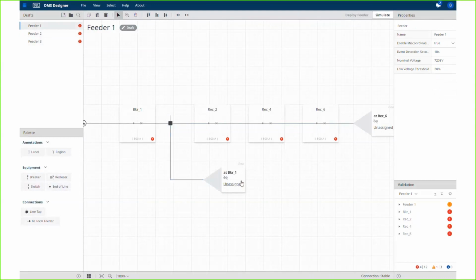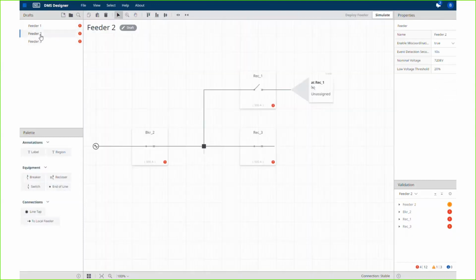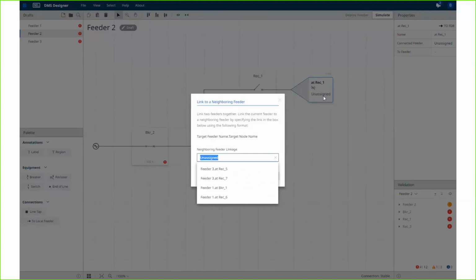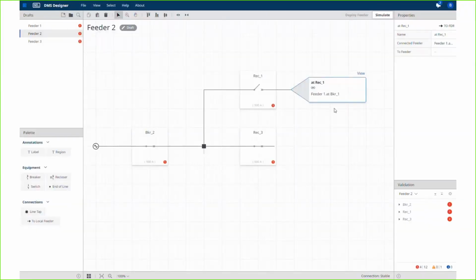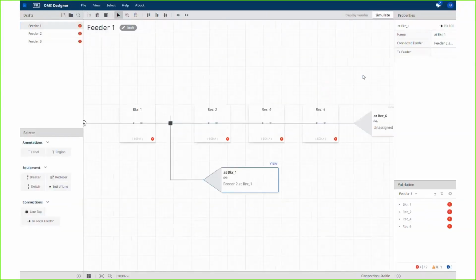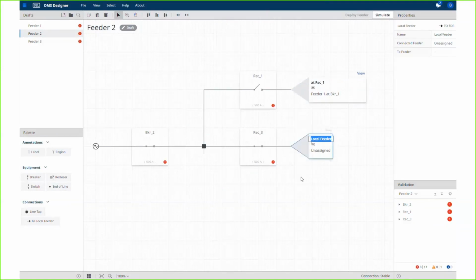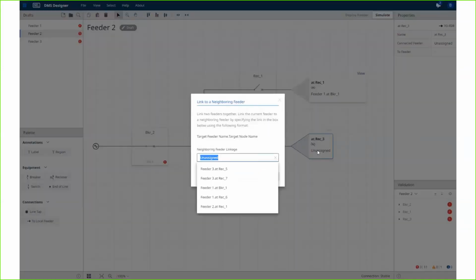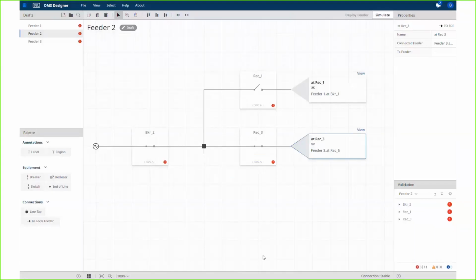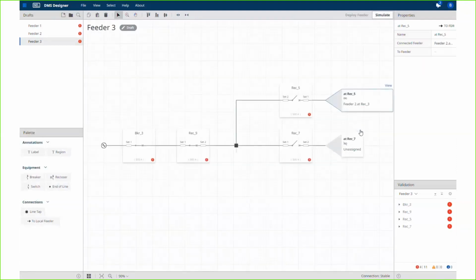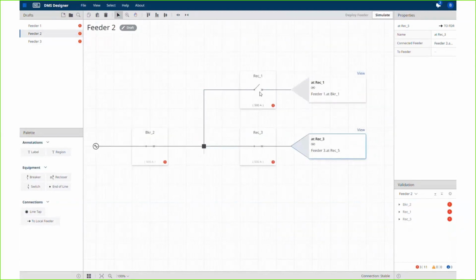So what I want to do is connect this neighboring feeder connection to this one over here. So what I'm going to do is glue them together or link them. So I'm going to connect this feeder 2 at rec 1 to its contemporary on the other circuit, which is called at breaker 1. It now knows they're connected and I can browse back and forth. So let's do this again. We're going to add a connection called at rec 3, and I know that that is connected to feeder 3 at rec 5. Rec 5 is the open point. Now we've connected these two together and I can browse back and forth between the two. FLISR knows that there's an electrical connection at that point now.